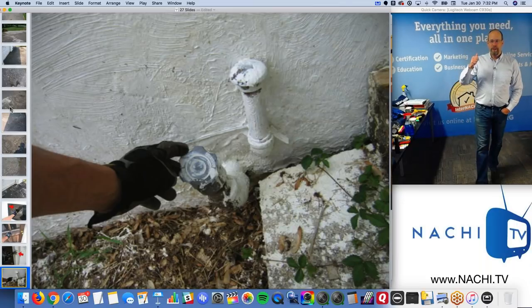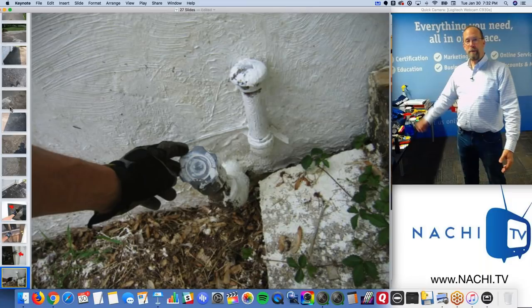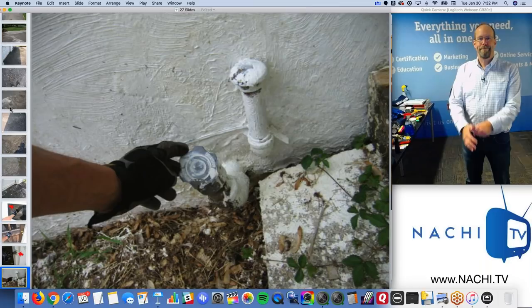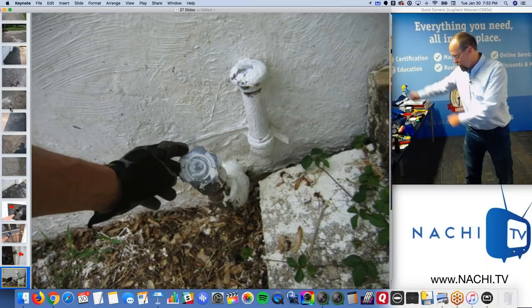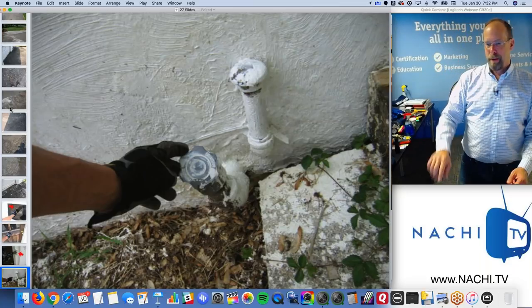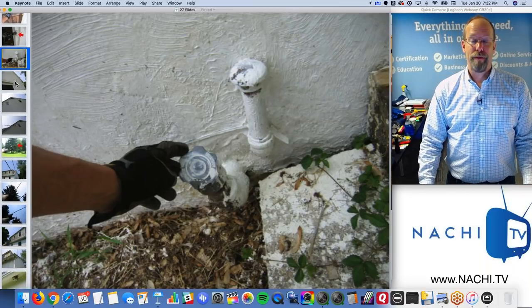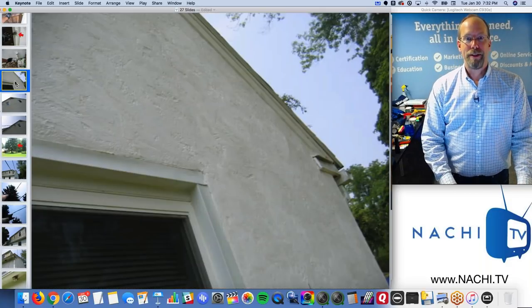We pump it out of the ground, and then we pump it into our homes and store it in a big tank. And then we suck it out of the tank, ignite it, burn it, and heat it for fuel. That's what we do in the Northeast. It's pretty crazy. Then as the tanker comes, he grabs a hose, he fills up the tank, he pushes oil into the tank, and air has to displace out, and that's the vent pipe. So that's the fun stuff of knowing something. If you're in Florida, or if you're in Puerto Rico right now, yeah, this is kind of like advanced training.